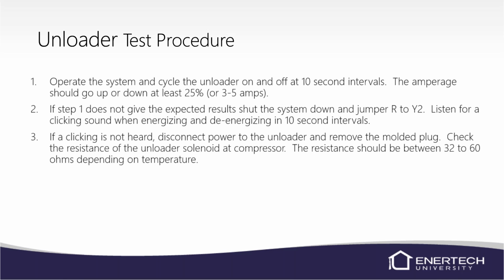You can also check the resistance on that molded plug, the resistance on the solenoid in the compressor. Basically, that resistance on that solenoid on the compressor itself should be about 32 to 60 ohms, depending on the temperature of the compressor. So the hotter the compressor is, the higher the resistance is going to be. If it's outside of that range, obviously there's something wrong inside of the compressor, and the compressor will have to be replaced.